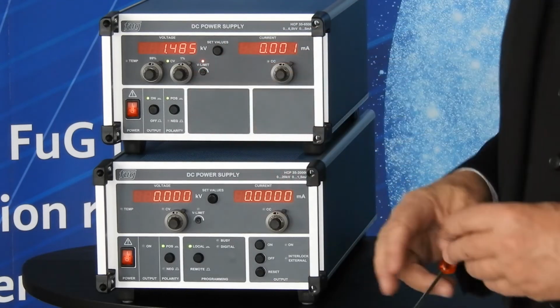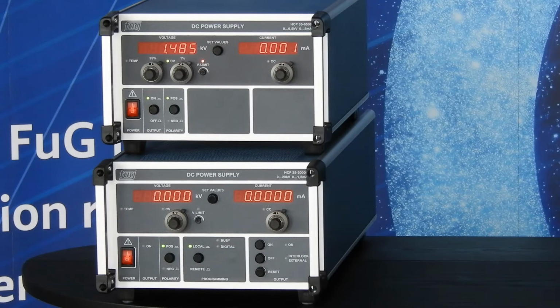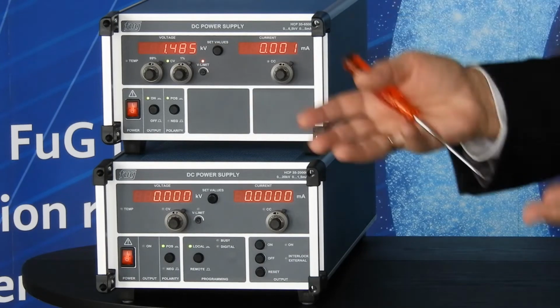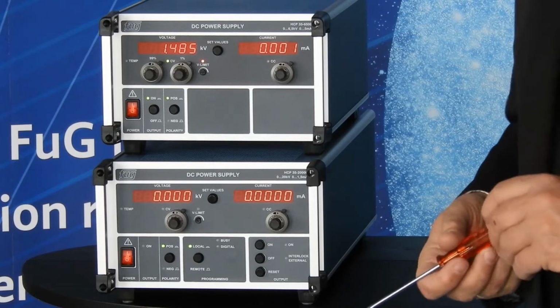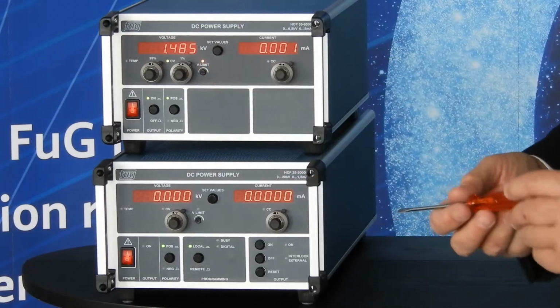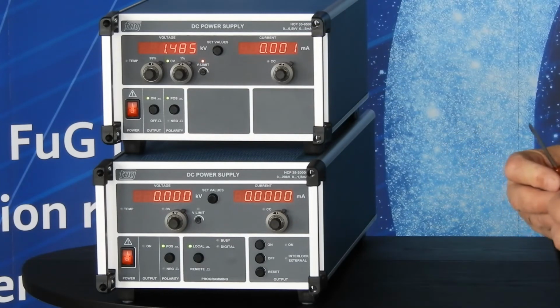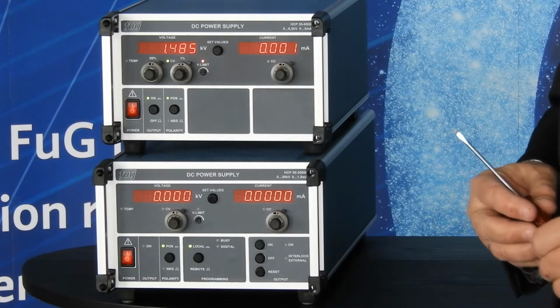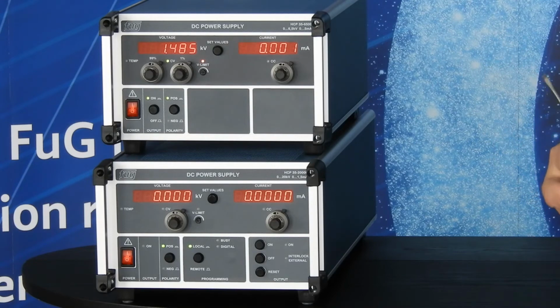This potentiometer cannot be overridden by any adjustment. Also, if the power supply is equipped with an analog or digital interface, even if the interface sends data requesting a higher voltage than is set on this potentiometer, it will not work. The red LED will go on and it will not deliver this higher voltage. So this can be used for some safety reasons, but please not for personal safety. For personal safety you must take special measures.